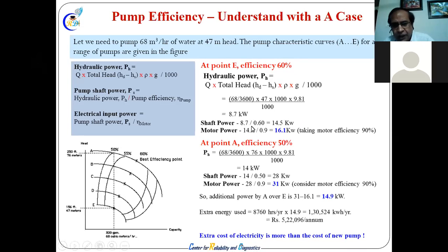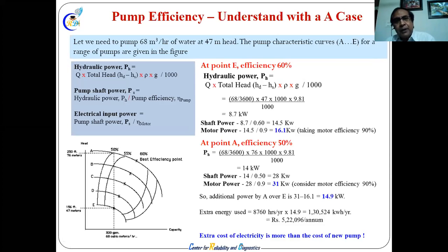And in the efficiency loss, if you take 60% efficiency, hydraulic power Q head rho G divided by 1000 gives around 9 kilowatt. Shaft power will be around 15 kilowatt, the machine driver you require. In the drive you get 15 kilowatt, but motor power required is 16 kilowatt, because everywhere there is an input-output difference. Okay, so that's why efficiency matters, and that's why motor power is much higher. For 9 kilowatt you need a 16 kilowatt motor with 60% efficiency, and with 50% efficiency it is much higher.